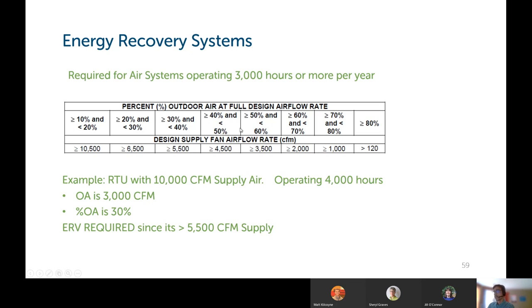So what you would do is at the top level of this table, find where 30% outdoor air is, and that's right here, greater than or equal to 30% and less than 40%. And if you follow it down here, if the design supply airflow rate is greater than or equal to 5,500 CFM, energy recovery is required. And the design supply airflow for this rooftop unit is 10,000 CFM. So based on this, this rooftop unit would be required to have energy recovery since it is supplying more than 5,500 at design airflow. So hopefully that helps describe how you would use this table for your different mechanical systems.